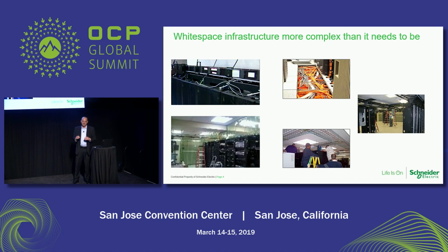All the fiber, all the cable, all the power runs across the top of that containment system. Then you bring the IT equipment in, do your rack and stack, your test, provision, and away you go. Now, if you want to do adds, moves, and changes, it's very complicated and almost impossible, because moving out a fully loaded rack from this rack-based containment system means you'd have to move all the cables, fiber, and copper running on top of it. So it's not only difficult and complicated, but also can be dangerous.